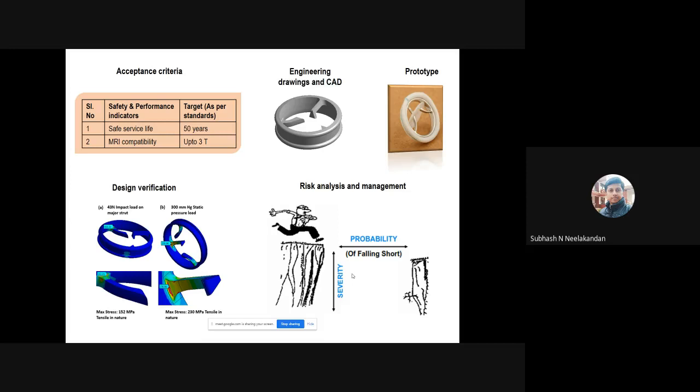So combining these three parameters, severity, occurrence, and detectability, the corresponding groups need to be identified, what the critical risk factors are, so that for identifying the risk factors and mitigating them, what are the various design verification activities that need to be carried out. So, in general, in medical industries, we can categorize these activities into three.